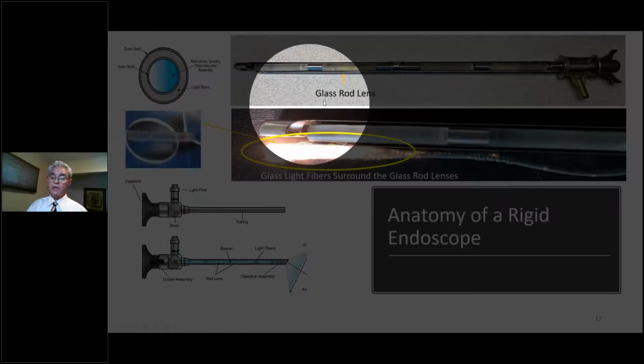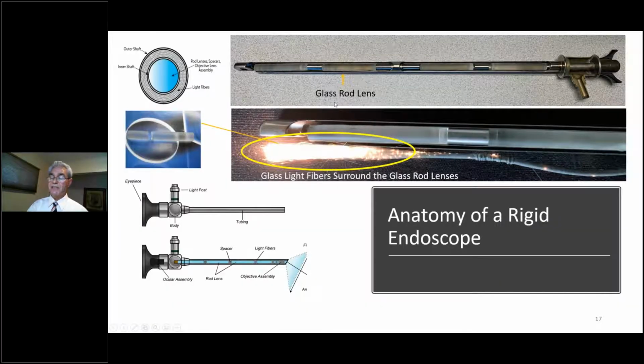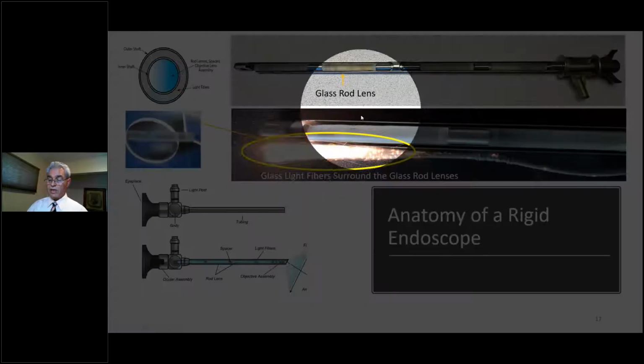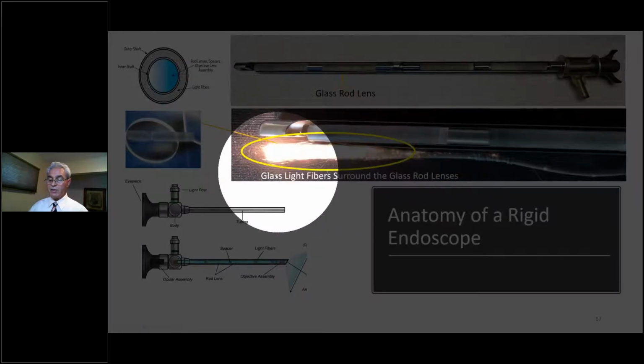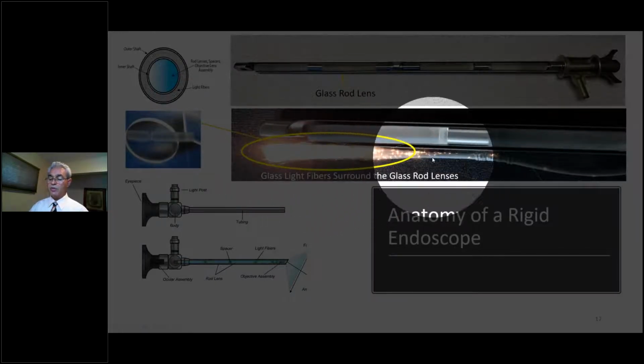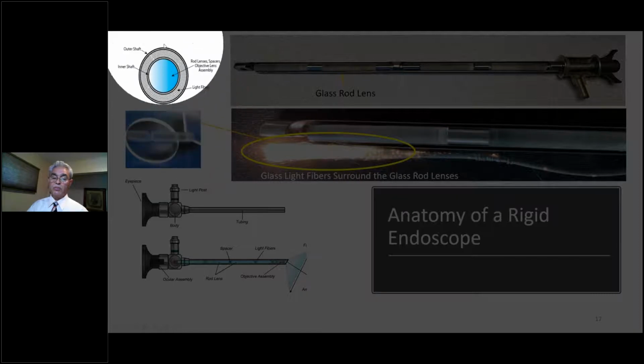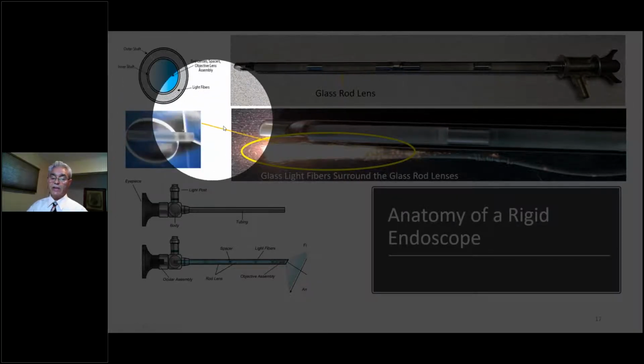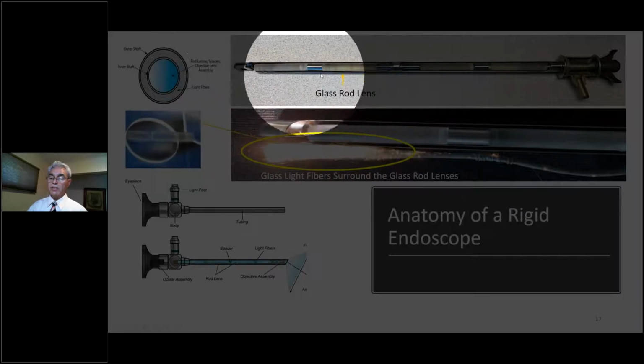And once it breaks, you're going to cause some basically distorted image of the device or the patient. So here, for example, on the flexible light fiber optic light source, as you see, some of these could break, and then you have black dots on the outside of that. So this is basically what is inside.